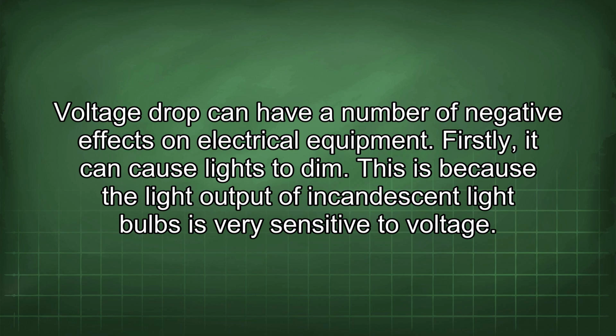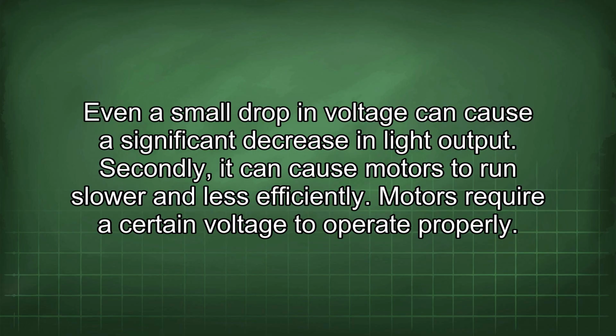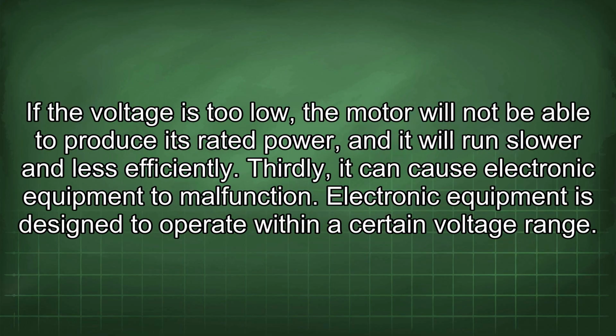Voltage drop can have a number of negative effects on electrical equipment. Firstly, it can cause lights to dim. This is because the light output of incandescent light bulbs is very sensitive to voltage. Even a small drop in voltage can cause a significant decrease in light output. Secondly, it can cause motors to run slower and less efficiently. Motors require a certain voltage to operate properly. If the voltage is too low, the motor will not be able to produce its rated power, and it will run slower and less efficiently.